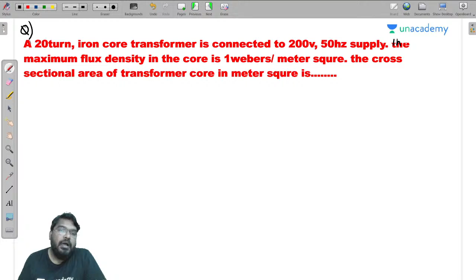Cross-sectional area of the transformer: here applied voltage of the transformer is almost equal to the EMF induced in the primary winding, if drop is neglected. So that is equal to 4.44 B maximum A N F.